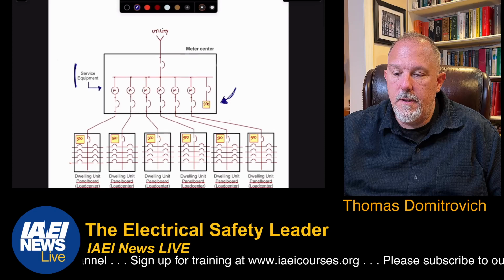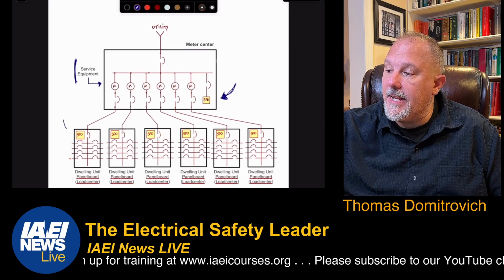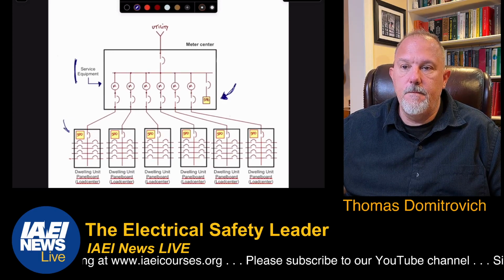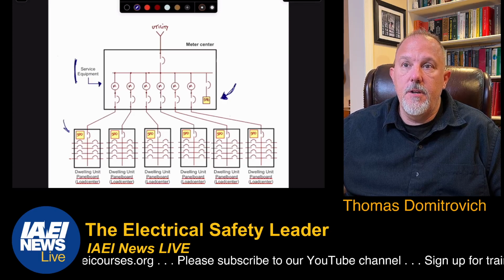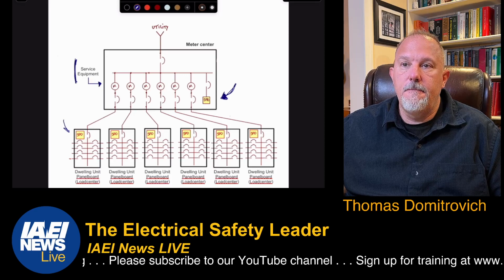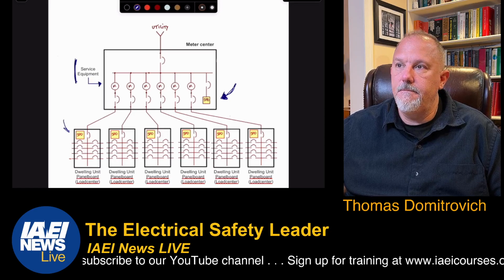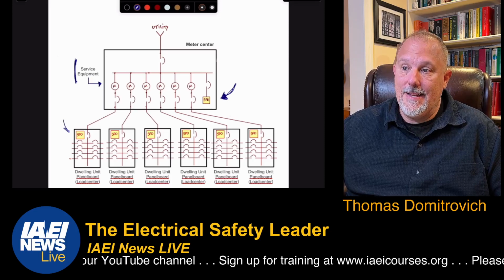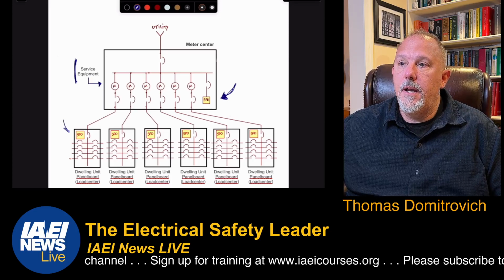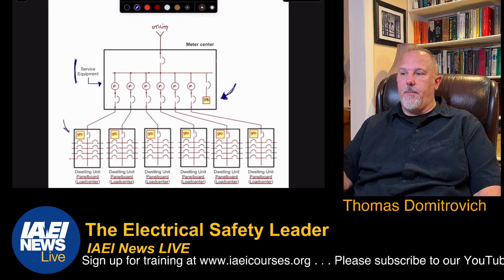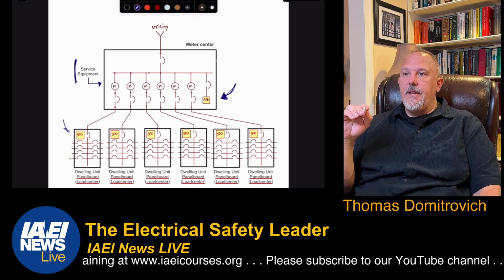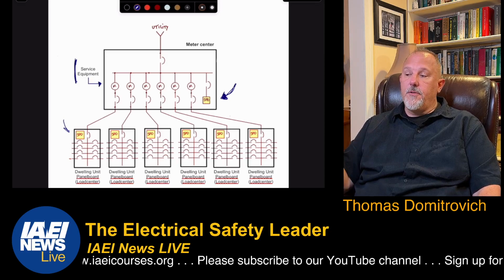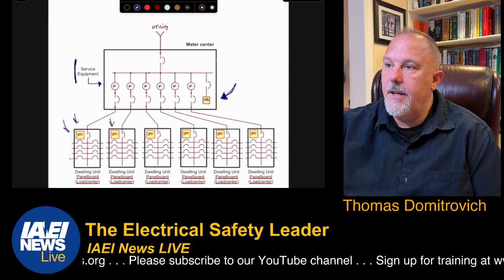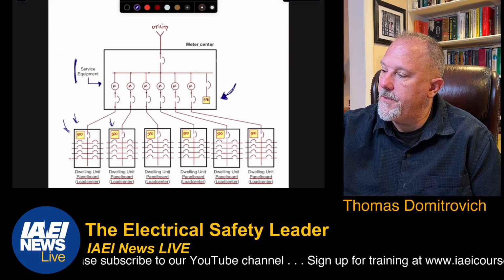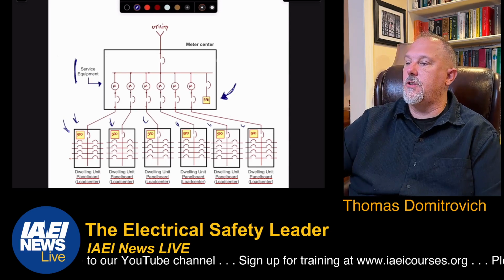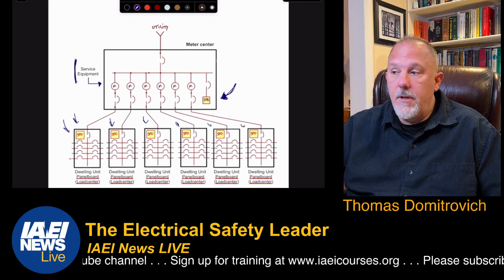But if I had an SPD at each of the downstream locations, so if I go to 230, where's 230? All right, 230.67. There is an exception in 230.67 that says, are you ready for this? The SPD shall not be required to be located at the service equipment as required in 230.67(B) if located at each next level distribution equipment downstream toward the load. That's the next level distribution equipment. If you have it at each of those locations, then you don't need the SPD at the meter center.